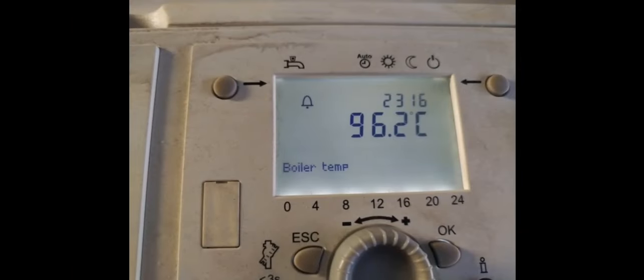One of the boilers, where you heard that noisy pump, the Wilo pump, wasn't getting the heat away quick enough and was making a humming noise and was pulling below 1 amp. The boiler was coming up with a fault indicator and the heat wasn't getting away quick enough from the boiler, so that pump's going to need changing.